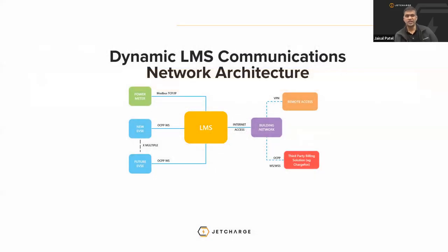So in terms of a dynamic load management system, they typically require a few networking architectures that are involved as well. So the power meters that monitor the incomer and outgoer circuits have to be connected to the load management system, typically by a category 6 cable, as well as individual connections from the chargers to the load management system via category 6 cabling. They connect through the OCPP protocol between the LMS and the chargers. And then the LMS also connects back to the building network to connect to the internet. This allows for remote access and remote commissioning by installers such as JetCharge, as well as third-party billing solutions like ChargeFox to ensure that people can either find the chargers online using their phone apps or be billed appropriately based on their usage. Next slide.